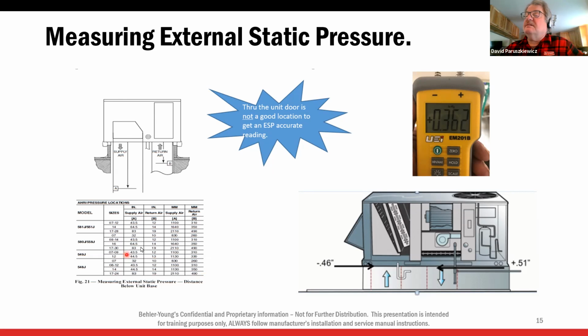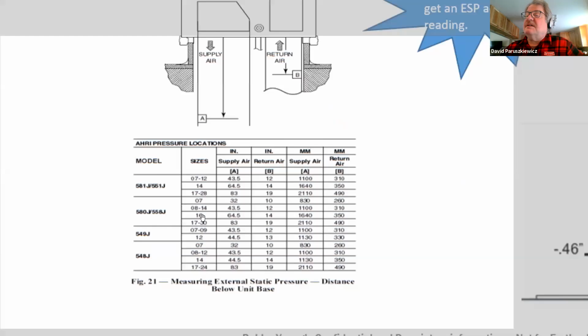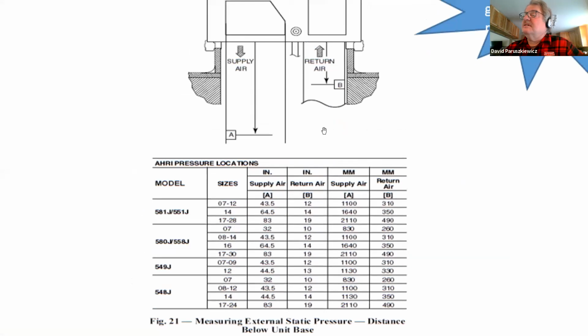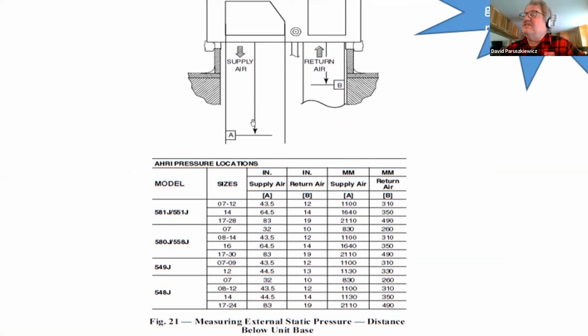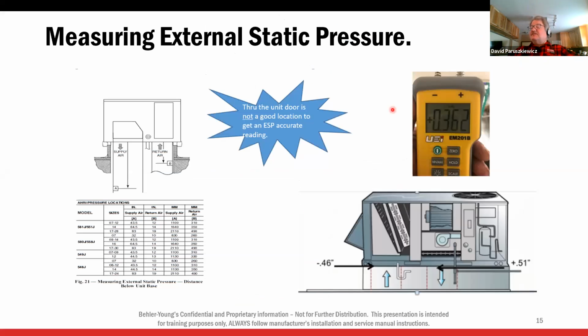This chart right here is out of the installation instructions, and it's going to tell us in the drop where they want us to check the static. They want us to check the static in the drops, not through the doors. It could be a 30% difference. I've seen a test done with it. So we want to get into the drop below the unit and the return below the unit, not into the doors. So we check our supply static. We check our return static.